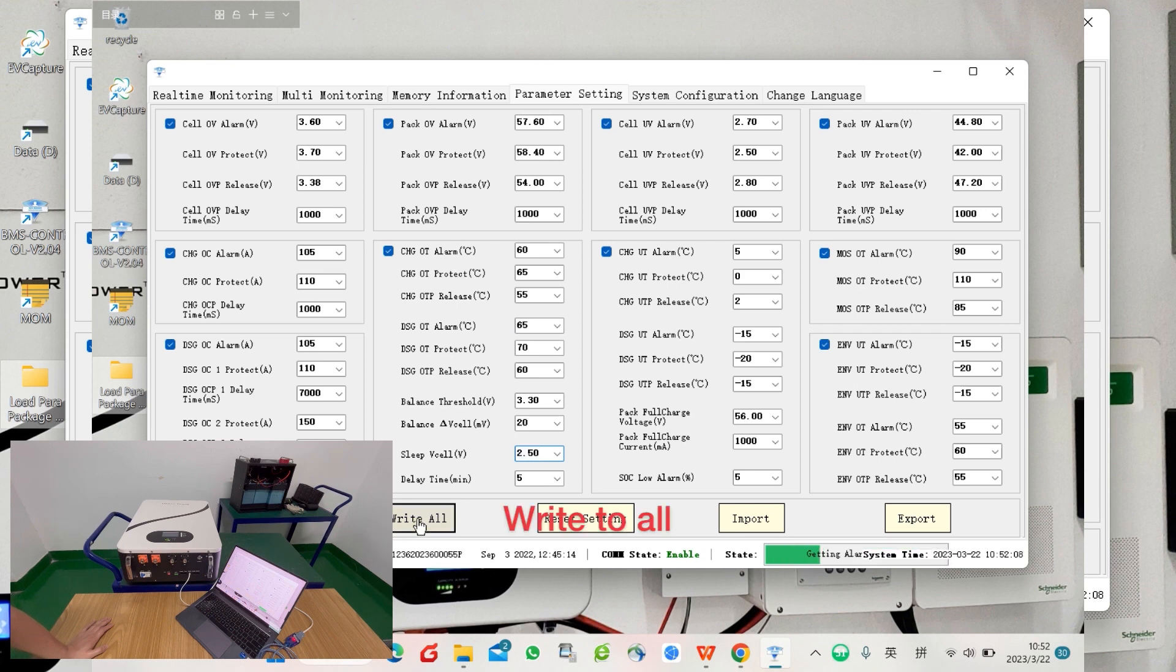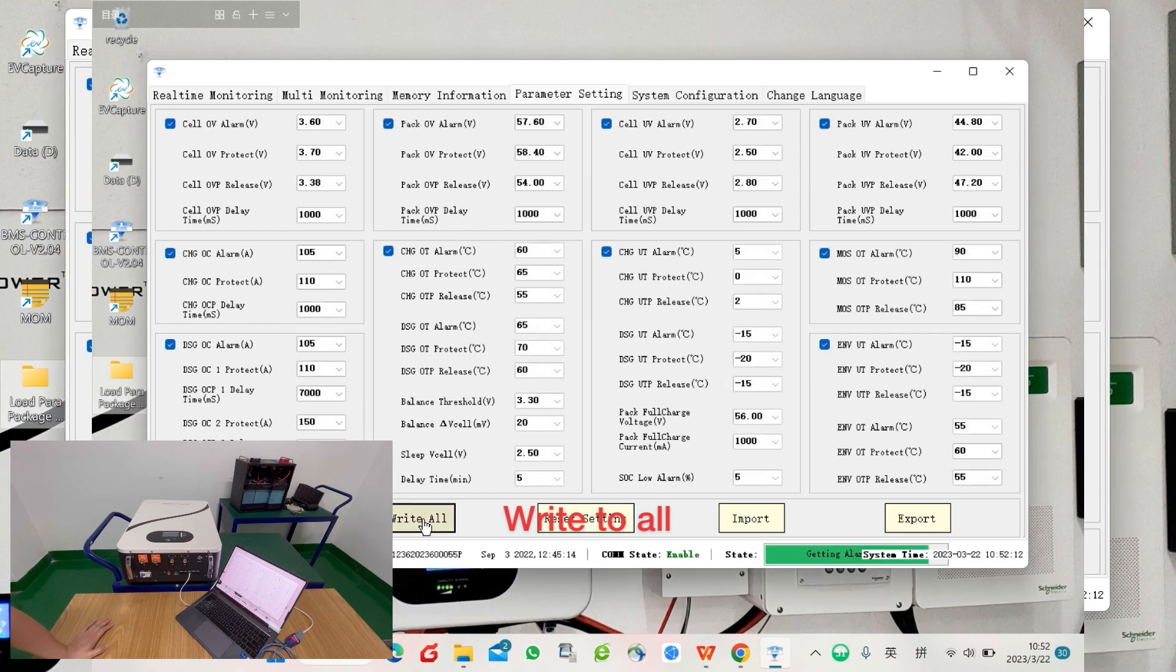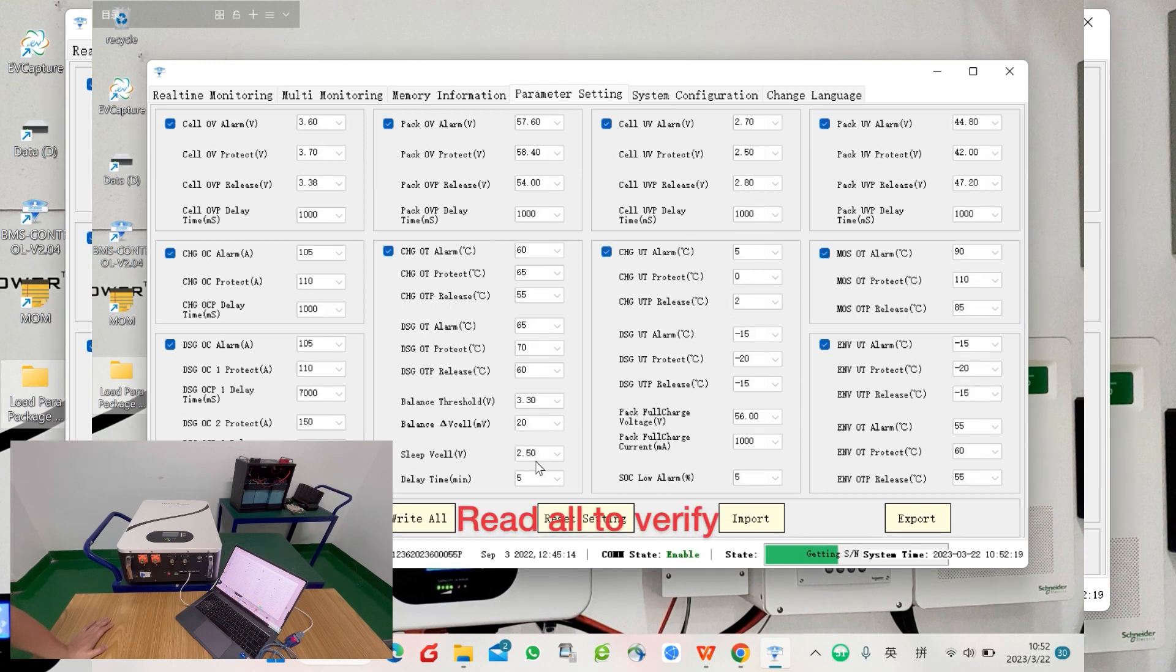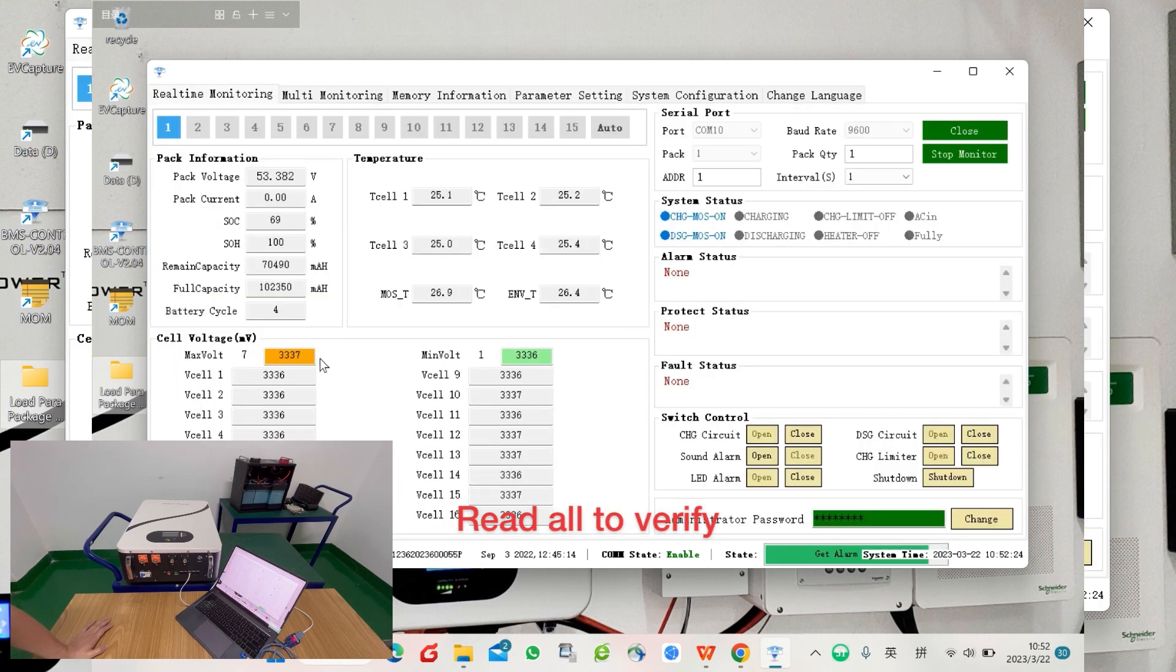Now you can start to write to all—that means download the parameters to the battery BMS. It's in progress. To verify, you can read all so all the parameters will be read from the battery BMS. You can verify the one which you have just changed.